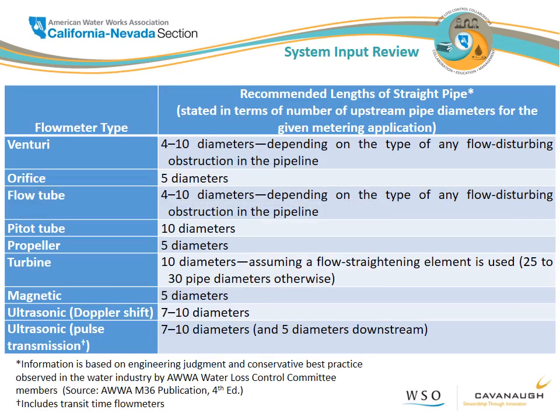Meters, again, depending on the technology, and this is another example of no technology being completely immune from all of these gremlins, generally require some degree of upstream and downstream clearance where it's straight pipe without the occurrence of something that would create disturbance in the flow, like a fitting, a bend, a valve, anything like that. So this is a big deal.